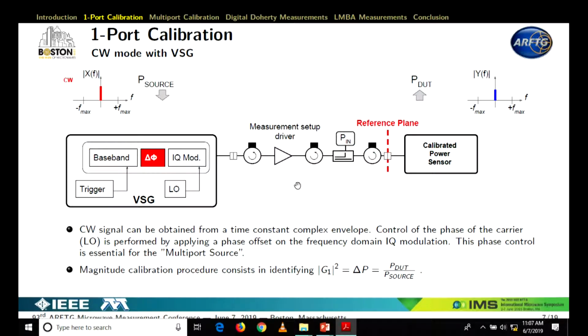So if you want to do one-port calibration in CW, this is pretty obvious, as I told you. You just have to put a power sensor in the DUT reference plane. And here, you just have to change the power level of the source, and you can identify the offset, whatever the driver here, between your command and what you have in the DUT reference plane. This gives you a power offset that is basically the gain between the command of the instrument and what is available in the DUT reference plane.